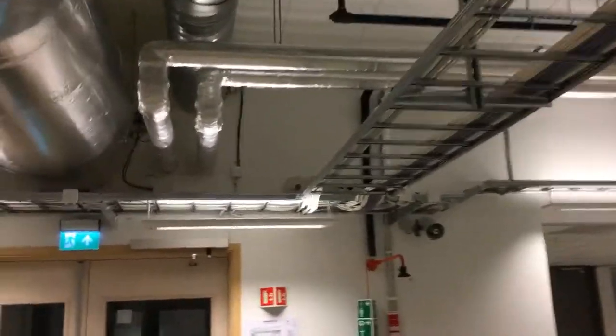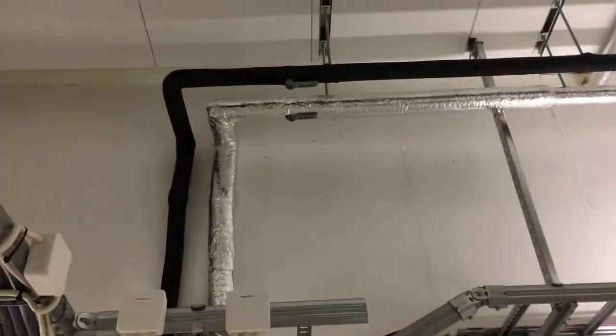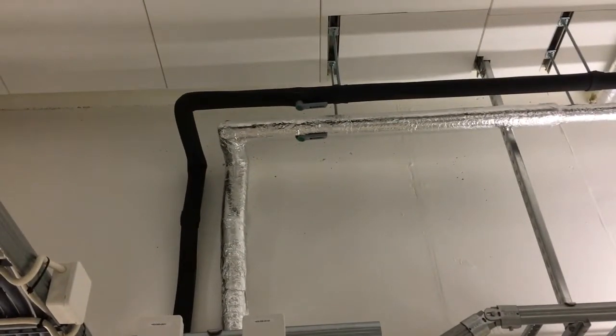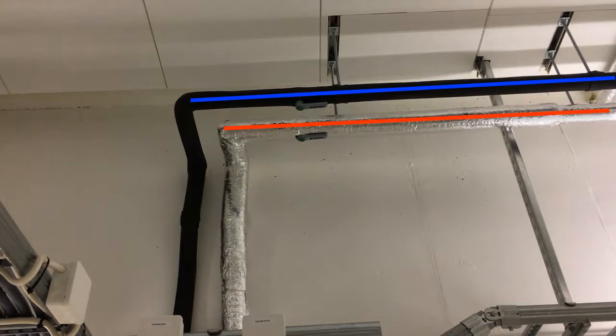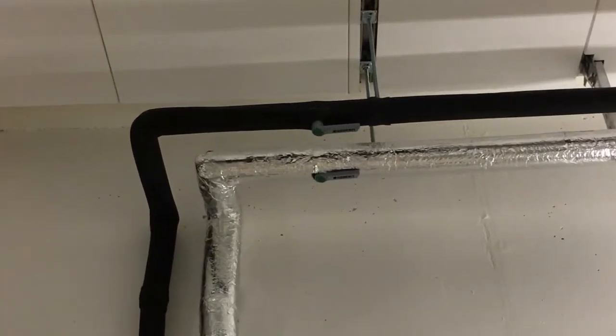Here's another piping system we can look at using the domestic water. There's some more interesting things here in the domestic water which is part of the safety systems in this laboratory. You see here two different kinds of insulation serving two different purposes. So this is actually a domestic water line coming in, this will be the cold water coming in, this will be the warm water coming in. The warm domestic water being insulated in order to keep the heat in, and the cold water line is insulated with a different type of insulation. It doesn't have the aluminum with a low emissivity for the heat transfer, but it does have this insulation which is preventing condensation on the pipe so that we don't get the cool pipe resulting in condensation and then drips of water falling down onto the equipment and electrical connections below.